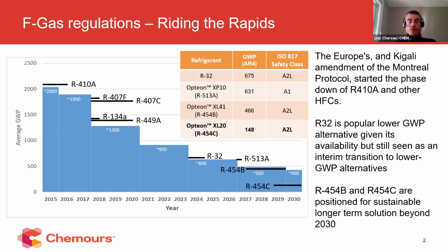As you can see, there are different choices when you look at the refrigerants we have from a GWP perspective, and the applicable solutions that can be seen along the years, down to 2030 and beyond. Within our portfolio at CHEMOURS, we have two products that we are talking about more and more with regard to new developments, which are the 454B and the 454C, the Opteon XL41 and XL20, with a GWP slightly higher than 450 for the 454B and below 150 for the 454C, which is a product that has been adopted by Stiebel-Eltron for their new heat pump.